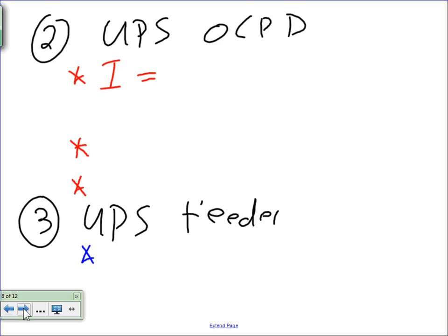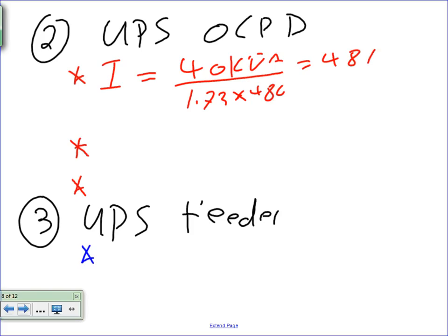All right, so now we know what the size is. Let's go size the rest of them. Since we're dealing with 40, take the 40 here, kVA, divide this baby by 1.73 times 480. I'm sizing the overcurrent device for that baby. And that will give me 48, right, Chris? 48 amps. And I'm going to assume it's continuous load, so multiply by 1.25 times the overcurrent device. 1.25 times 48.